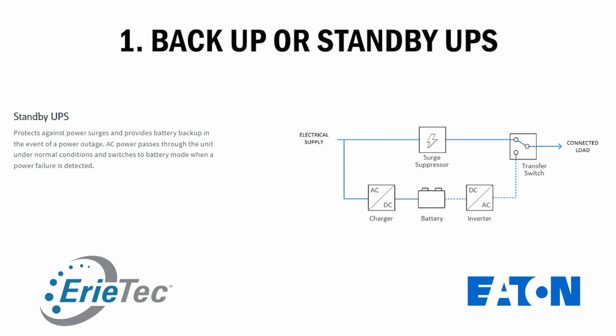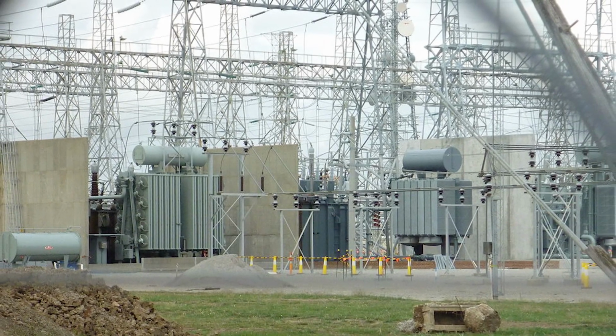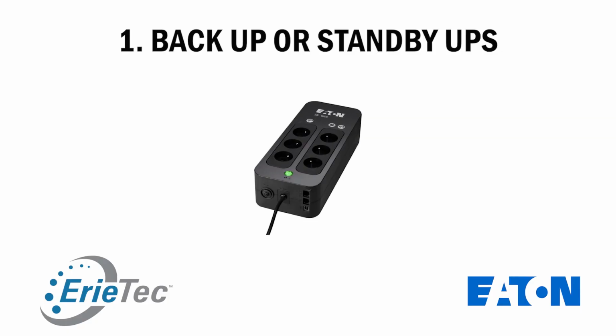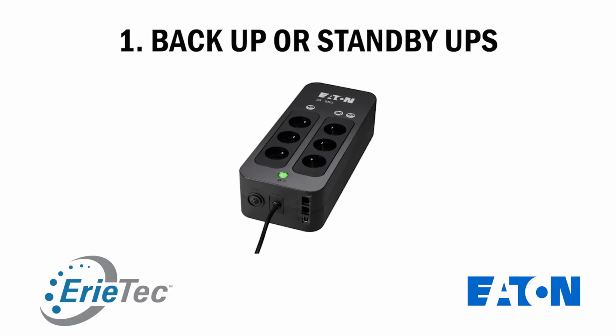The first type is what's known as a backup UPS or a standby UPS. It is simply a box like this. It has an inverter and a battery, a small battery charger, and a contactor. Under normal circumstances, the utility is fed straight through the box to the load. When there's a power outage, or if the voltage increases or decreases by a set amount, the inverter kicks on, the contactor opens up, and the battery carries the load for a short period of time, typically in the range of 3 to 5 minutes. When the utility comes back on, the contactor closes, the inverter goes off, and the battery starts recharging. That is the most simple UPS, and it really doesn't do anything other than provide a short backup.